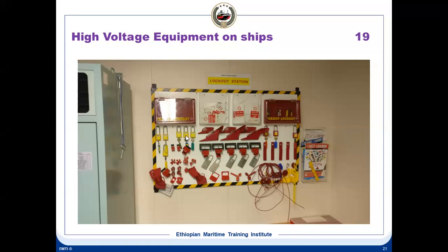So suppose 3 people, 1 engineer and 1 electrical also working, then you can use these locks for locking the systems, like breaker locking or some valve locking, etc. And this is the individual one. If only 1 person is working, it is red locks. These are the various types of locking systems, like this is for breakers, this for valves, etc. And these are the notices you will find here. Whenever you work in these high voltage systems, you have to take out this one and write your date and what you are doing; everything has to be tagged on. So this is a lockout station.